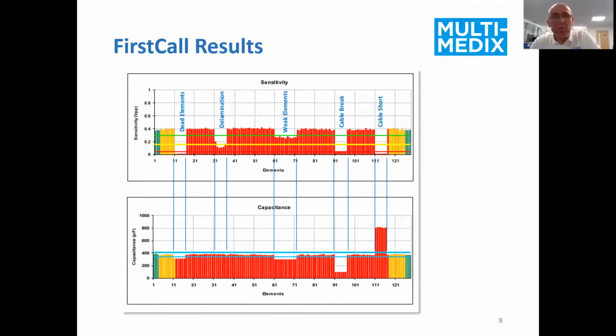So let's move over to this slide, which is one of the most important on the webinar today. What it allows us to do, if we get a mix of low, medium or high sensitivity, and the same with capacitance, and we look at their adjacencies, is start to diagnose not only that there's something wrong, but what's wrong. On the first part of this graph, if we completely lose sensitivity and have no acoustic performance, and a small drop in capacitance, by understanding the electronic characteristics and makeup of the probe, we can define that the remaining capacitance is made up of the cable, because the cable is the main part of the capacitance. So a small capacitance drop means we've got an open circuit where the element is, and a lack of acoustic performance tells us we truly have non-functional or dead elements in their truest sense.